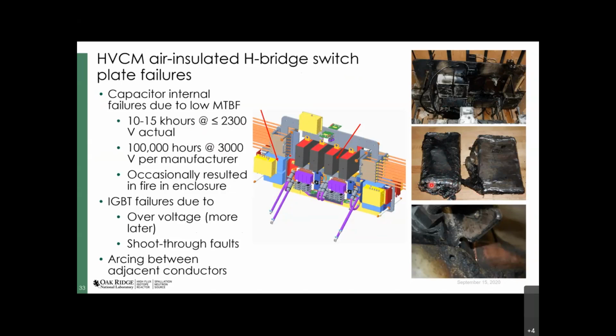That would, of course, cause the case to fail. The case, in some cases, contained a rather flammable dielectric fluid, and so that would drip near the surface, and if arcing ensued, which did in this case, you had an ignition source, you had a combustible material, so obviously you're going to have a fire, and that's what happened.